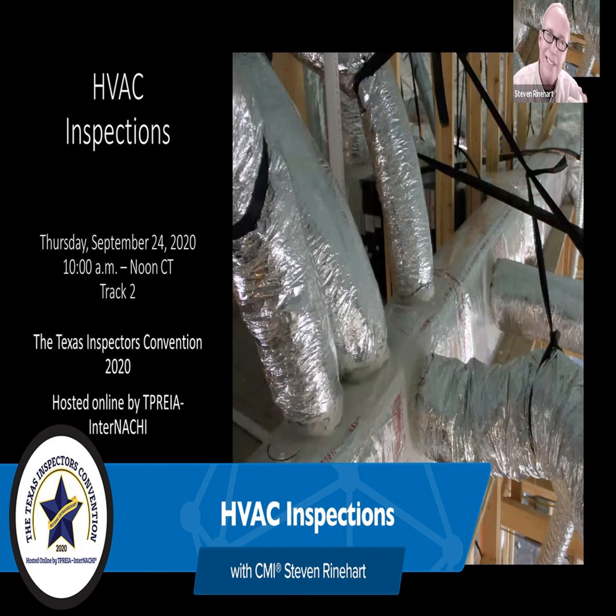And I say, why do that to yourself when you can run that condensation probably from the attic right out of the soffit down to the ground, even in a retrofit? So I do make a note. If I see condensation going into the inner part of the sewer drainage system, I make a comment that it is a defect. I just think the scenarios are too bad.